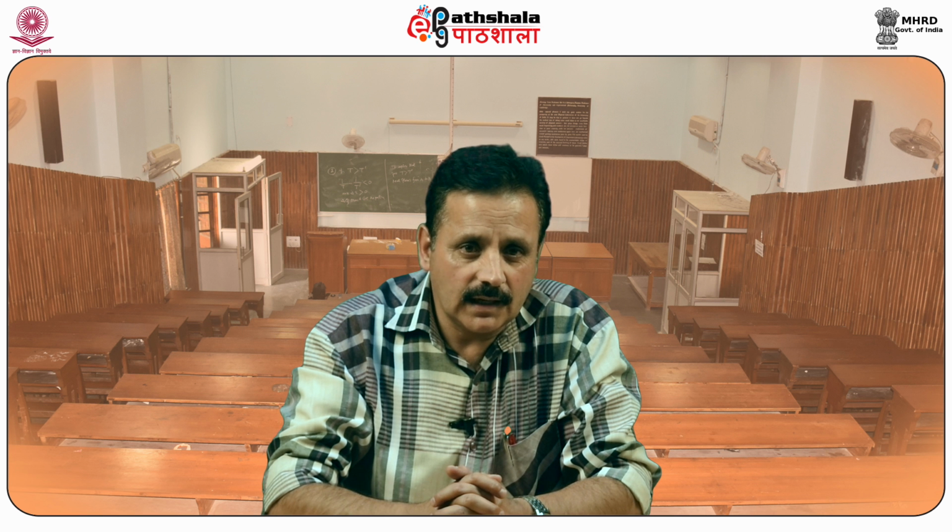The functioning of the photomultiplier tube is based on the well-known principle, the photoelectric effect, which converts light energy into electrical energy. A photomultiplier tube consists of a light-sensitive photocathode which emits photoelectrons at a rate modulated by the signal, and a multiplier section which amplifies the signal to provide a measurable current output.